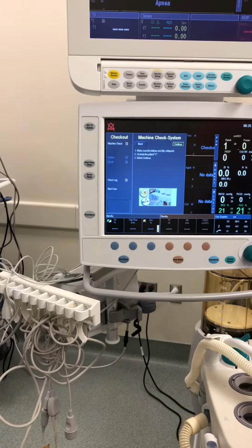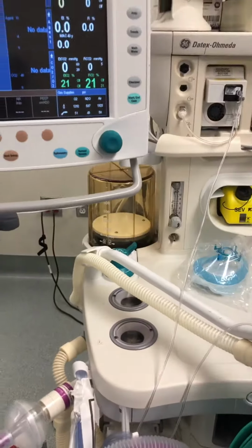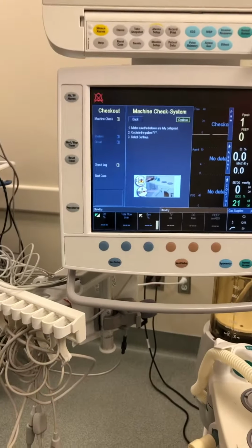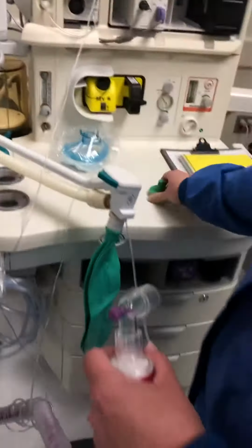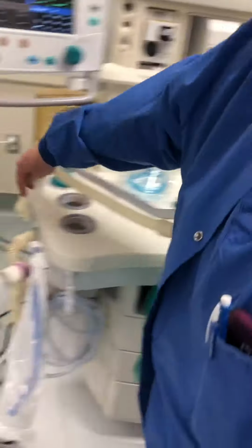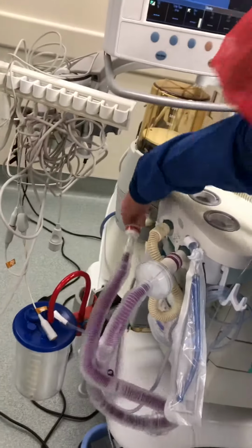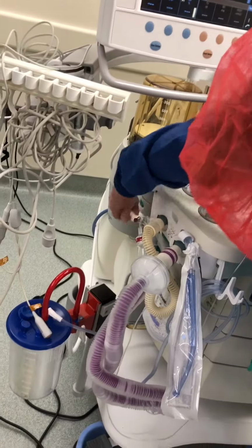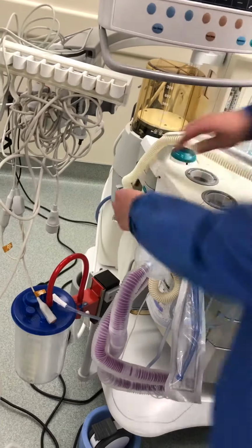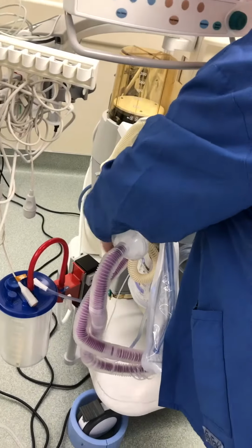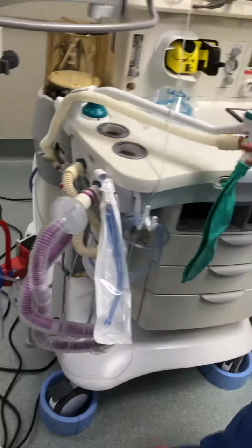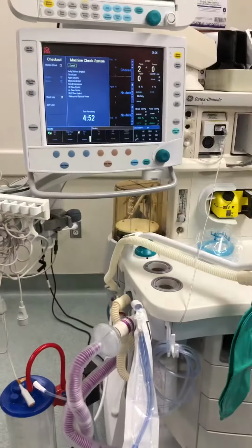So you just want to make sure and visualize that the bellows are fully collapsed. And then you want to occlude the patient Y. They've been using the green plug, but I'm actually going to use the little thumb port right behind the expiratory flow sensor. I'm going to make sure all these connections are nice and tight because there was that leak, just to rule that out, and then select continue.